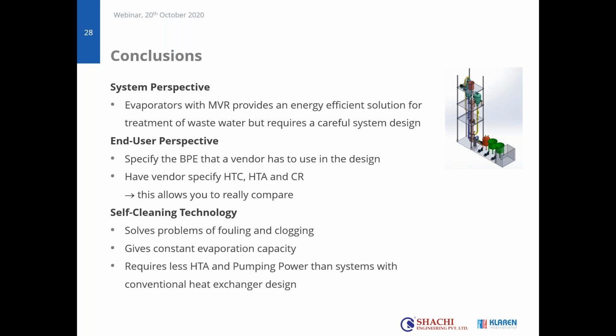The last conclusion is, of course, what we are very passionate about, which is the self-cleaning technology in combination with the above. With the self-cleaning technology, we can solve the issue of fouling and clogging. We can get a plant that has a constant evaporation capacity. And we can have a plant that requires less heat transfer area and pumping power than systems that have a conventional design. So at the end, there will be a very good business case from the end user perspective.